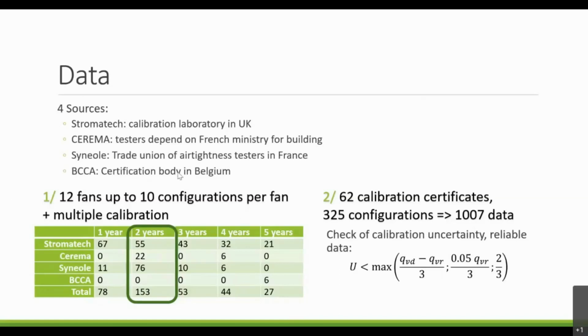For the first part of the study, it was much more difficult to gather data because we needed the fan to have been calibrated at least twice in a certified laboratory to be able to plot the deviation between the first and the second calibration. So for this first part of the study, we have 12 fans only and up to 10 configurations per fan. Some of them have been calibrated more than twice. So at the end, we get 153 values for the deviation after 2 years, which is the most data we had, so we have performed the statistics for the deviation after 2 years.